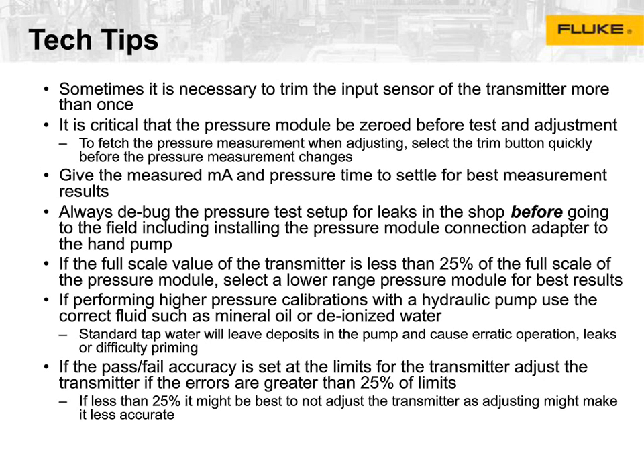And last but not least, if the pass-fail accuracy is set at the limits of the transmitter, adjust the transmitter if the errors are greater than 25% of its limits. What this refers back to is the TUR. Basically, what it's saying is that if you set it at its limits, and you're seeing errors greater than 25% of limits, you probably don't have sufficient TUR to do the adjustment, and by adjusting the transmitter, you're going to end up making the transmitter less accurate than it already was. What you need is to go get a higher accuracy system, so either more accurate pressure modules, or you need to be able to move the limits in order to make that happen.